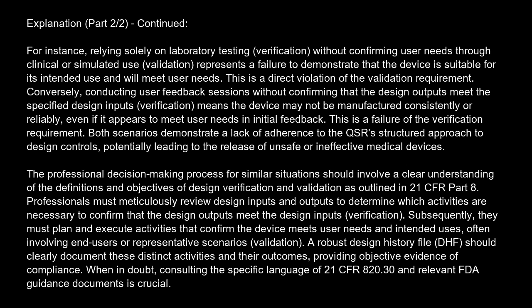Conversely, conducting user feedback sessions without confirming that the design outputs meet the specified design inputs (verification) means the device may not be manufactured consistently or reliably, even if it appears to meet user needs in initial feedback. This is a failure of the verification requirement. Both scenarios demonstrate a lack of adherence to the QSR's structured approach to design controls, potentially leading to the release of unsafe or ineffective medical devices.